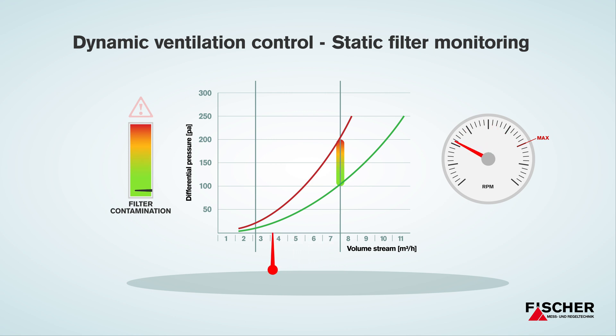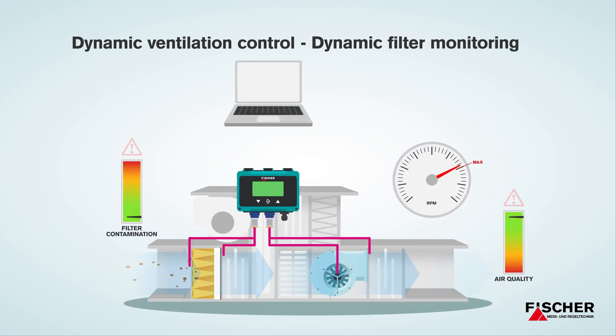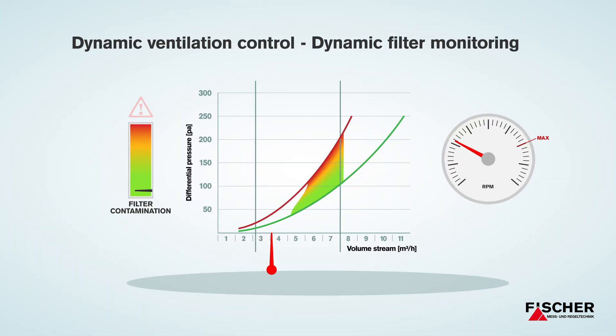Until now, your ventilator had to run at full capacity for this reading. As a solution to this, we developed the dynamic filter monitoring. The Fischer DE90 software can precisely evaluate the results of your system's volume stream together with the difference in pressure of your filter. So, for the first time, you have the possibility to precisely measure the contamination level of your filter at any time during operation.